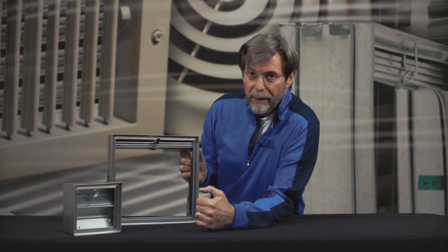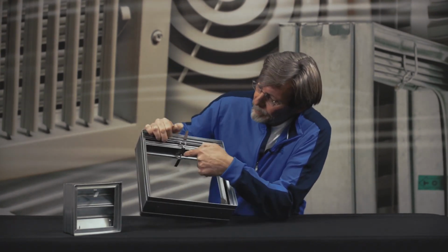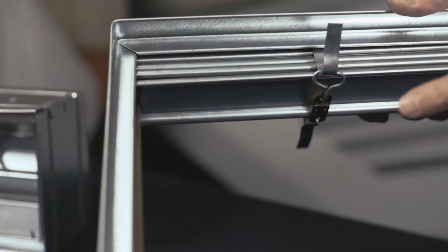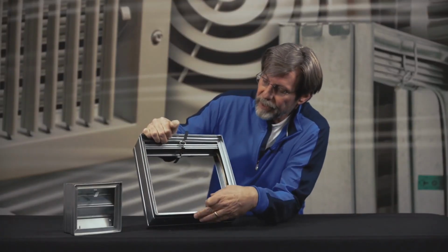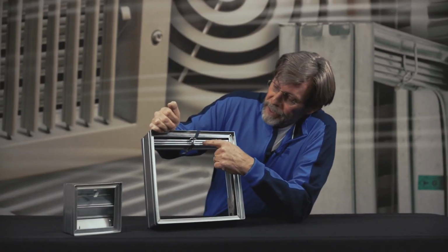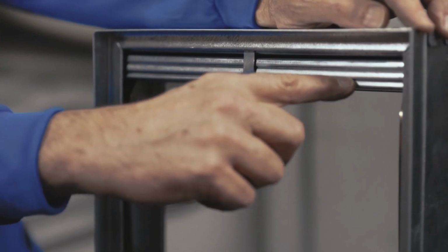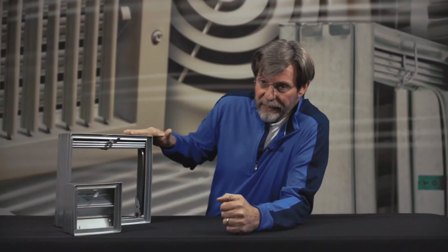This is also a type A damper. In this case, the blade stack is open. It's being held in place by a fusible link. The fusible link, if it gets up to temperature set point, it opens. That allows this blade stack to close and create that metal curtain. When you look at this though, you can see the blade stack is in the airstream, and this is going to act as a resistance to airflow. So the type A damper doesn't have the same airflow characteristics as a type B or type C.